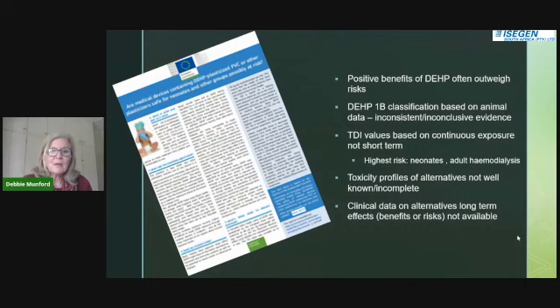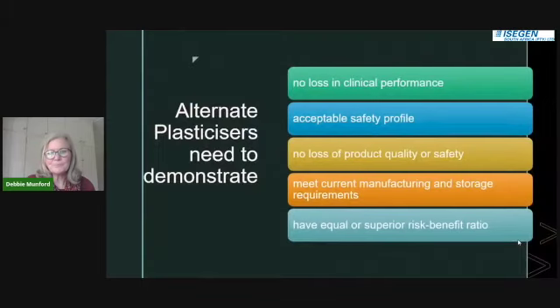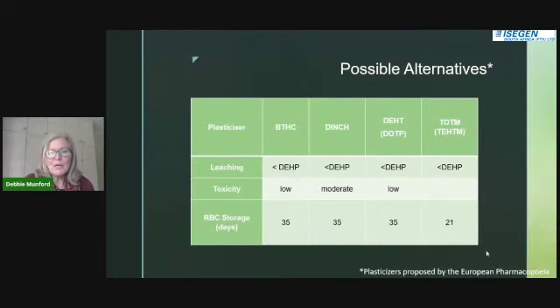It often takes a long time to establish these, and there's obviously a risk versus benefit trade-off. So alternate plasticizers need to demonstrate, when it comes to medical devices, that there's no loss in clinical performance, that there's no loss in product safety or quality, that current storage, for instance, particularly with blood, is maintained, that their safety profile is acceptable, and that they obviously have a superior or at least equal risk to benefit ratio. And this is something that's been quite difficult to do because a lot of the processes and procedures are not that well in place to be able to do this and to study the alternatives effectively. It also takes a long period of time.